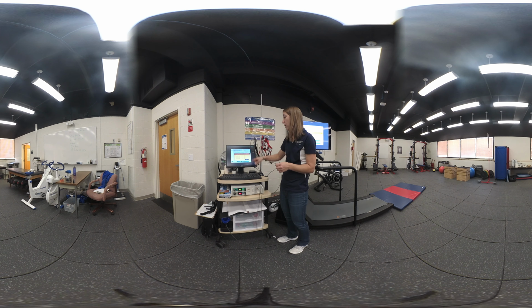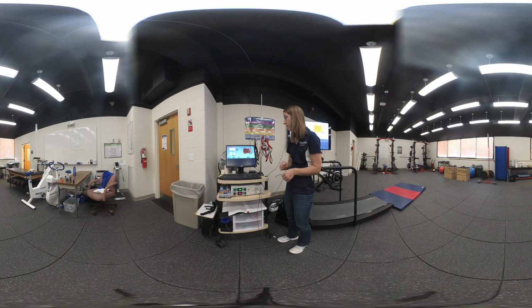And then you can go on and make sure, once you're confident everything's working in your own setup, if you had a previous poor calibration compared to what you have now, it will tell you what's expected and what the actual is. So the actual numbers, if you're doing everything correctly, should be close to what the expected are. So if these are way off from your calibration gases, and particularly these are the voltages, you might have an issue of when some of these dials have been touched that were preset at the manufacturer, and that would actually require going back to the manufacturer to have that fixed. So usually that is not a problem whenever you're going through this. When you're ready to then start your test, you're just going to click exit to test screen. And now you can go on and you can plug in your subject's information and you can get all started.